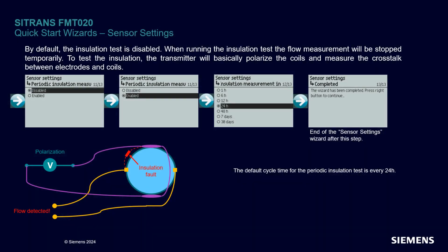The last step of the sensor settings wizard is to control the insulation measurement. If you choose to enable it, we recommend performing the in-situ adjustment for better performance. This value is measured at a regular interval of your choice. During the measurement, the H-Bridge is driven with a signal and the product expects no signals on the measurement electrodes. If a flow were detected, it would mean there is an insulation fault in the electrical circuit. An averaging over 512 measurements is required, which takes approximately 45 seconds to complete.